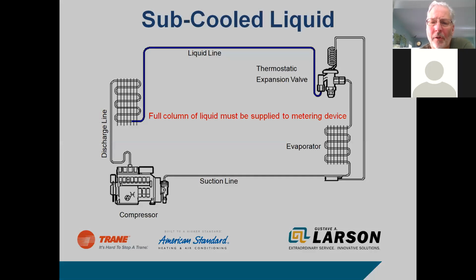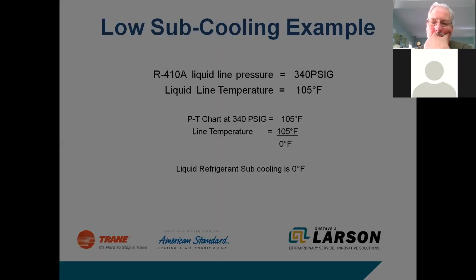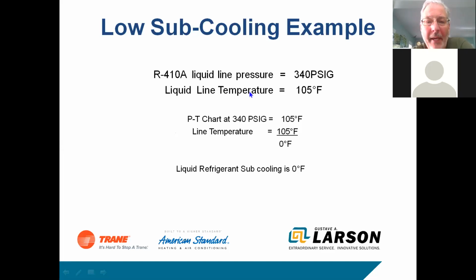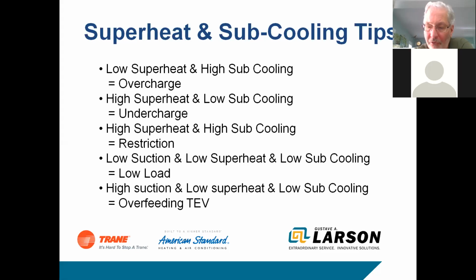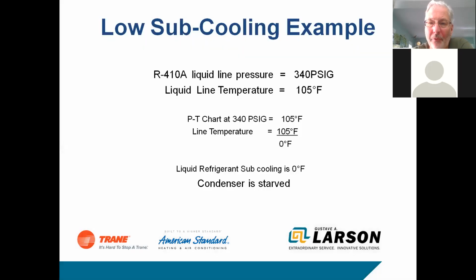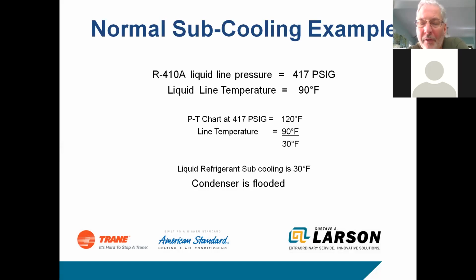And as long as we're doing it, let's take a look at this. If I have a system and I'm looking at the subcooling to make sure it's charged properly, I've got an R410 liquid line pressure of 340 and liquid line temperature 105. I've got a PT chart that shows 105. The actual line temperature is 105, so I have no subcooling at that point. My system is starved. It's undercharged. So the lower the subcool, the lower the charge. The higher the subcool, as in the next example, the higher the charge. No, previous example, sorry. Yeah, the higher the subcool, the higher the charge.